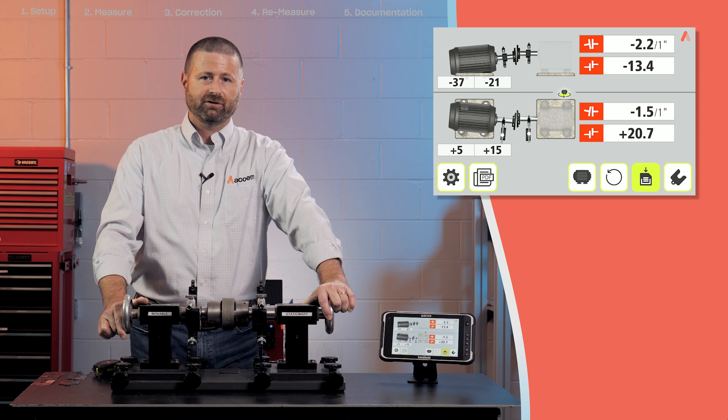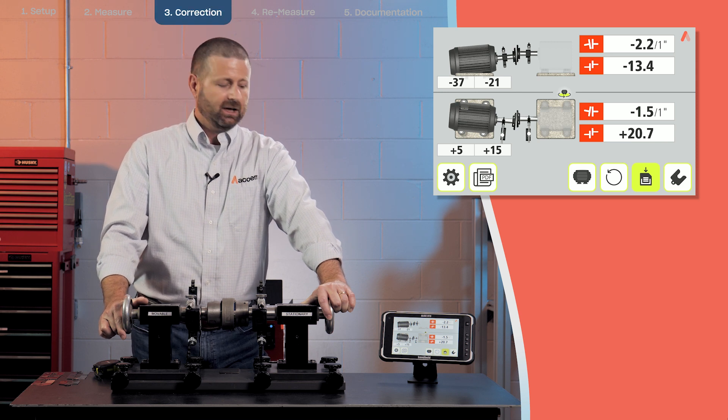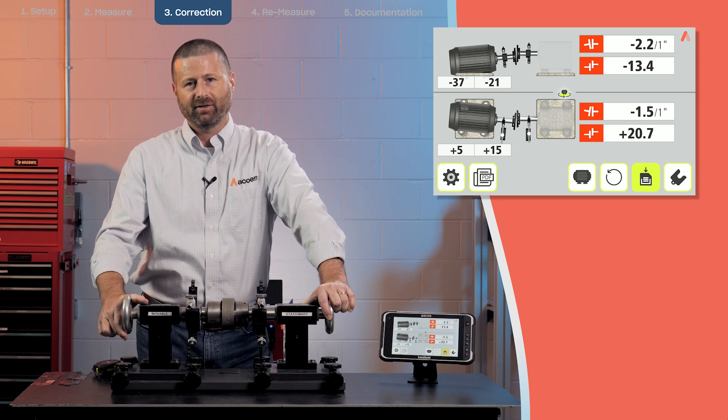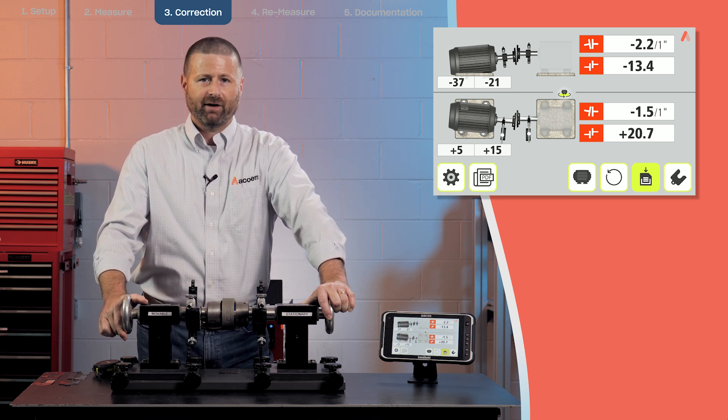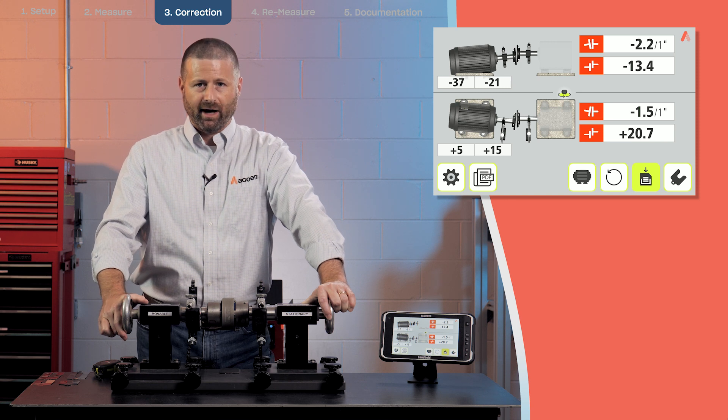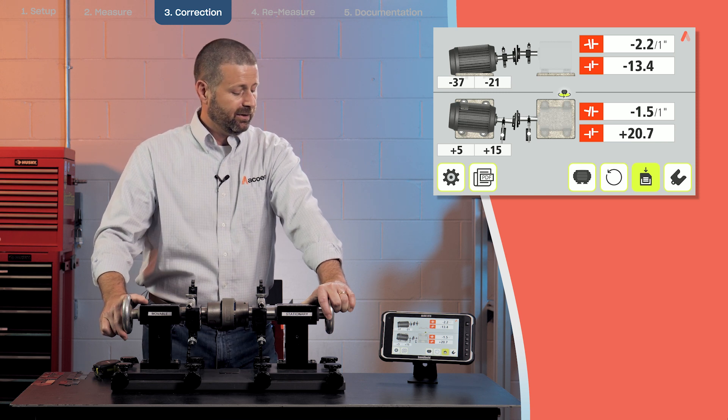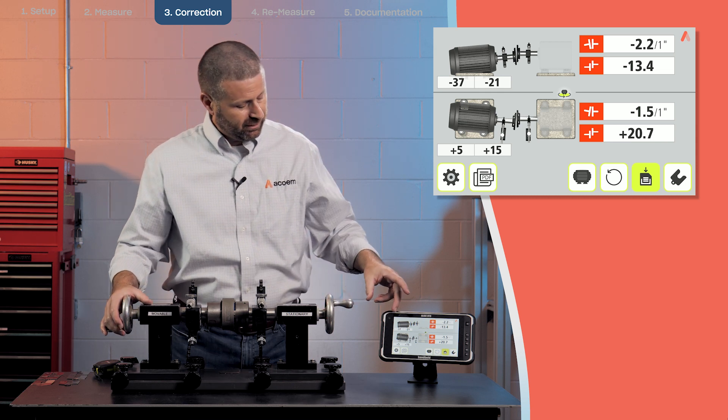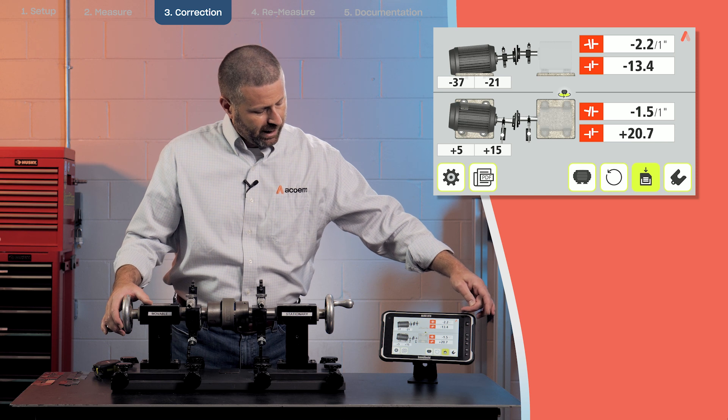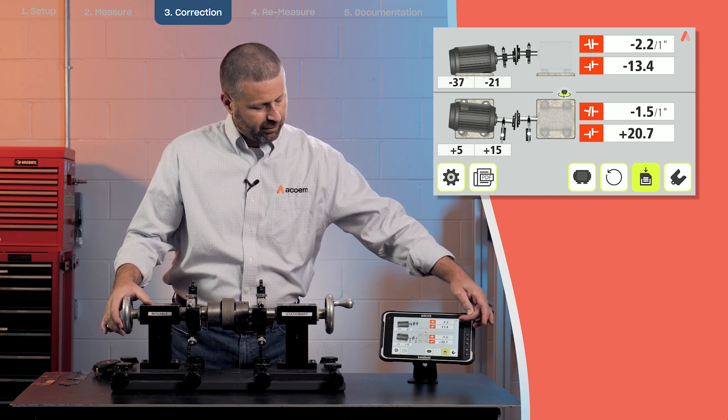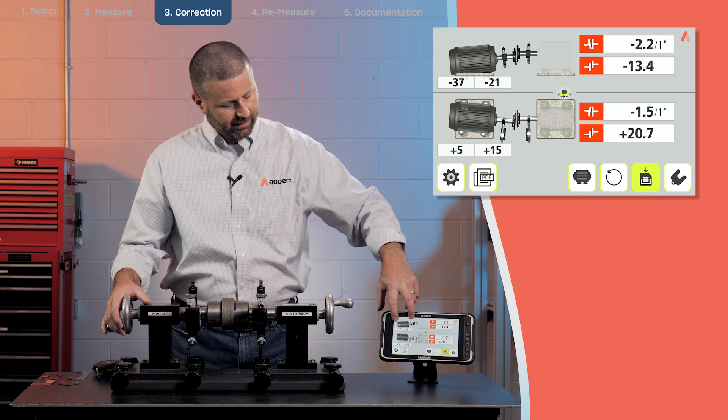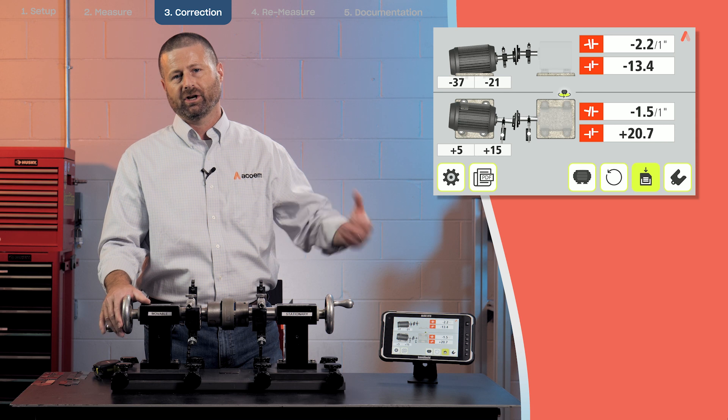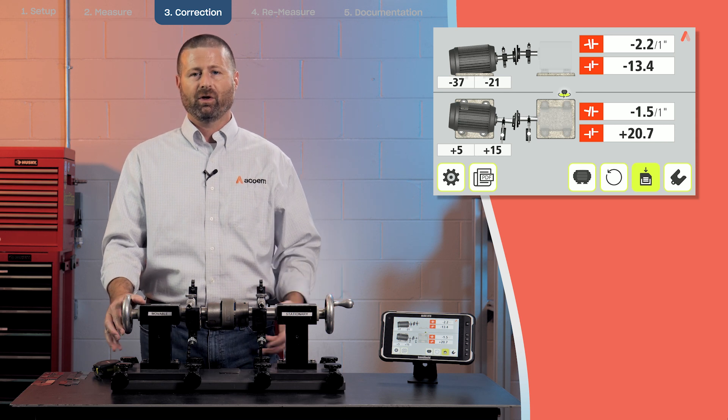So now we have a presentation of data. What you can see is all red, meaning that all of my values are outside the tolerance. The top set of values are the vertical values, and the second set are the horizontal values. This is where the angle and offset are vertical angle and offset horizontal. The numbers underneath the machine feet indicate how much I need to adjust the machine to get them within tolerance.